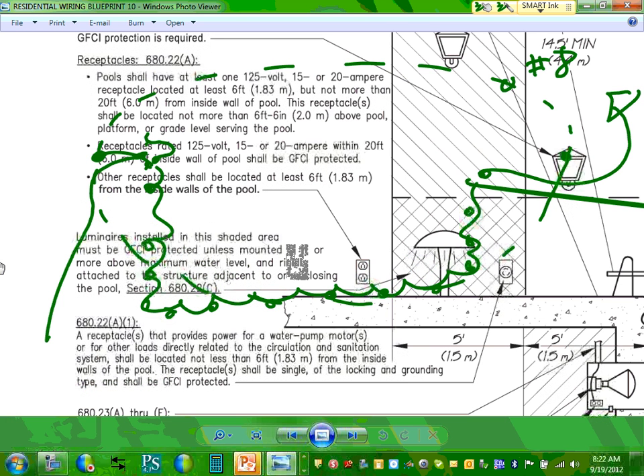Okay, you're right, absolutely. So typically we don't put them more than that, but it's there too. Otherwise it would be impossible to reach it too. So not closer than 6 feet, not further than 6 feet high, and it has to be GFCI. Any comments? Any questions? Like everything else, Kerry, it's in the code, my friend. This is just an introduction. When you have a project that has a swimming pool in it, and you are the project manager, Joe, you know what you need to do? If that were my project, I would review this one from A to Z as a project manager. Does it make sense, guys?